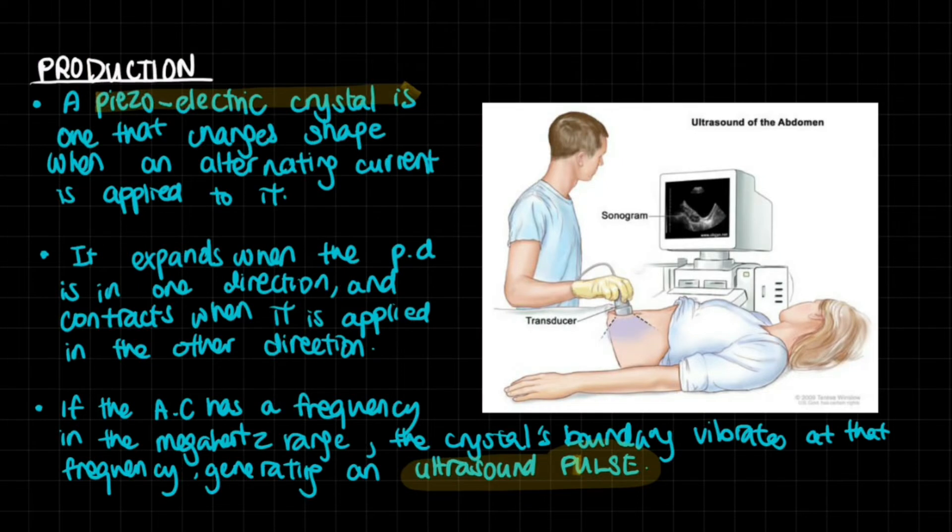How do you produce ultrasound and get this photo? The main character is a piezoelectric crystal - one that changes shape when an alternating current is applied to it. It expands very slightly when the potential difference across it is in one direction. Reverse the potential difference direction and it will contract very slightly. If your alternating current has a frequency in the megahertz range, the crystal will expand and contract at a frequency of a few megahertz - millions of times per second.